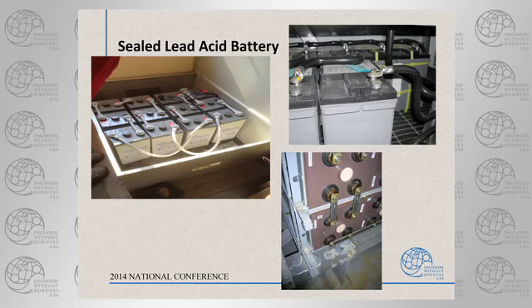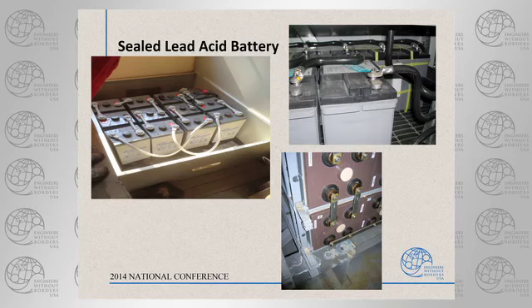Other examples of sealed lead acid product. These little 12-volt jars, and you go, well, that looks pretty good. Yeah, that's in a high voltage UPS. But what we've got right here, I've got a big lug and a small battery terminal. Now, in electrical systems, you generally figure 1 square inch of copper will let you flow 1,000 amps through it. Now, when you're dealing with a lead-plated product, okay, be charitable, cut it back a bit, but we're dealing with a battery post here that's maybe 5/8 of an inch in diameter, circular, and this particular string was designed where 300 to 400 amps had to go through that battery string. That's not enough conductive area. Those posts will get hot, real fast.